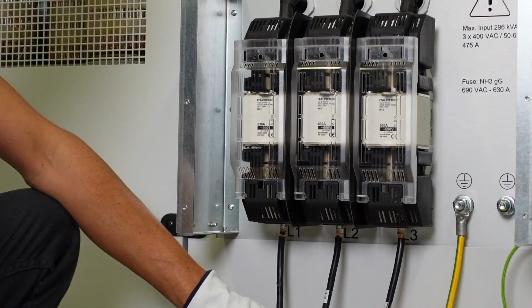Take off the back panel. Now we've already connected it, so as you can see we have the input cables here. Just make sure before you do anything on the back side, you disconnect the mains input. Very important. Disconnect it, open the circuit breakers, and make sure no one can reconnect it before you do any installation on the mains.